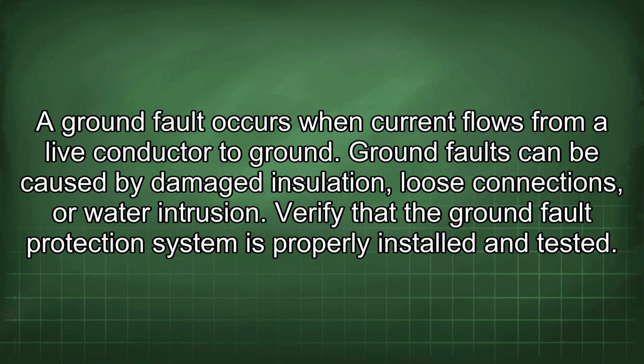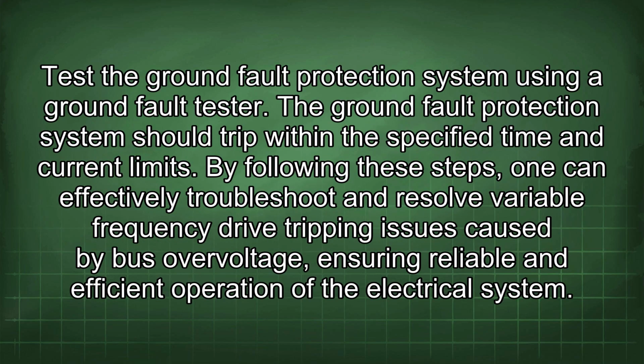Verify that the ground fault protection system is properly installed and tested. Test the ground fault protection system using a ground fault tester. The ground fault protection system should trip within the specified time and current limits.